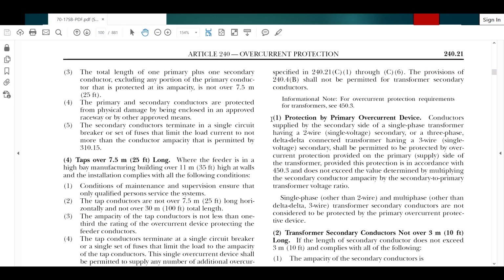Now let's look at this one. Here's the first one. All right, so 240.21 C1, this one right here. This is a weird rule because this is one that allows the conductor supplied by the secondary side of a single-phase transformer having a 2-wire and a single voltage secondary, or a 3-phase delta-to-delta connected transformer having a 3-wire single voltage secondary, to be protected by overcurrent protection provided on the primary, the supply side of the transformer. Okay? Provided, again, that this protection is in accordance with 450.3, and we've shown you how to do that in part 2 of the episode. Okay? And of course, it does not exceed the values determined by multiplying the secondary conductor's ampacity by the secondary to primary transformer voltage ratio.